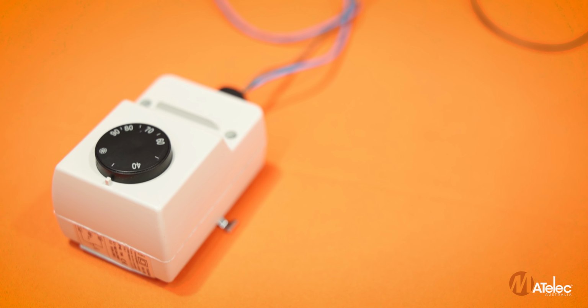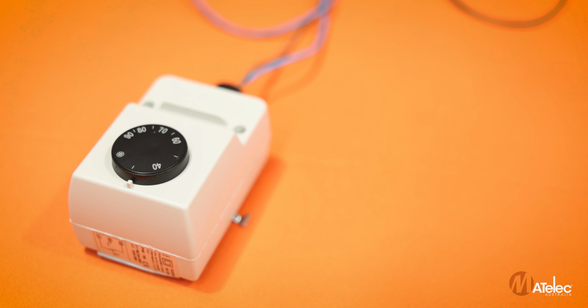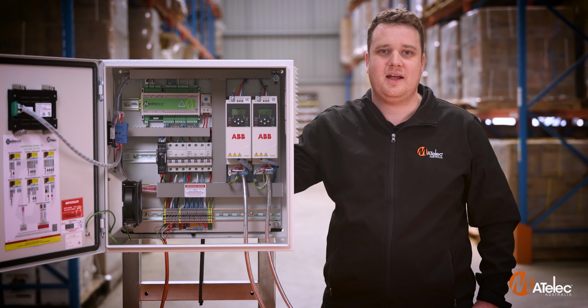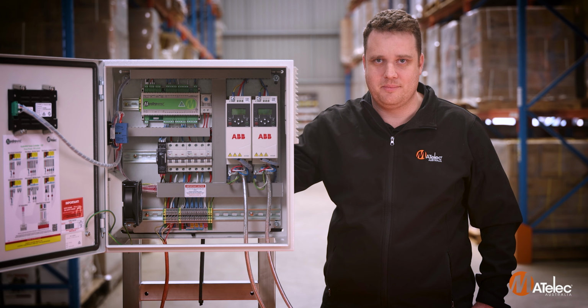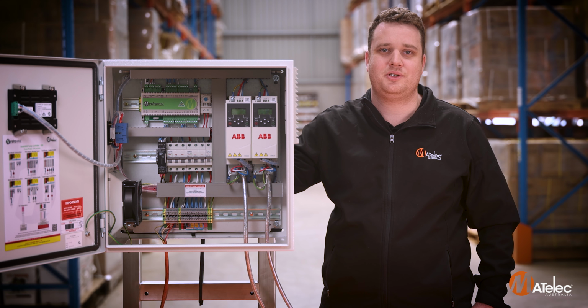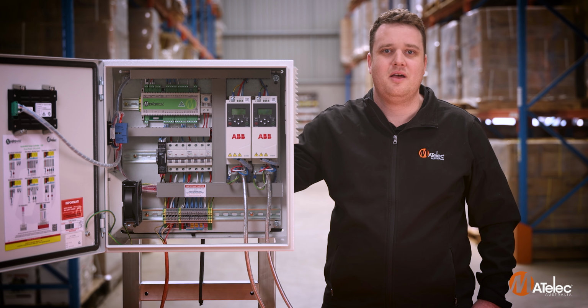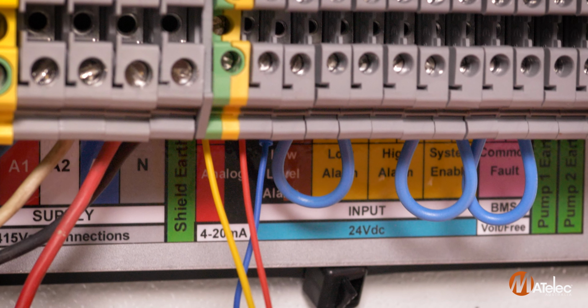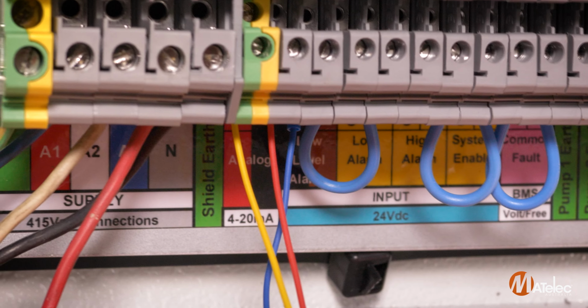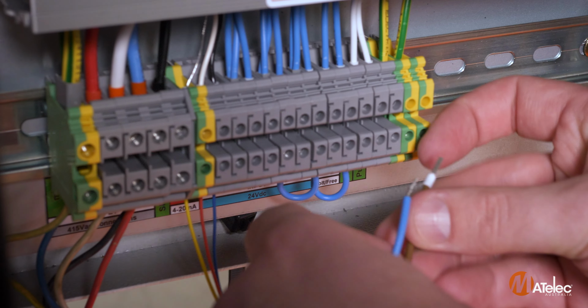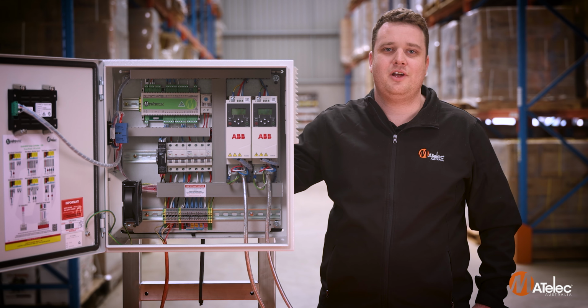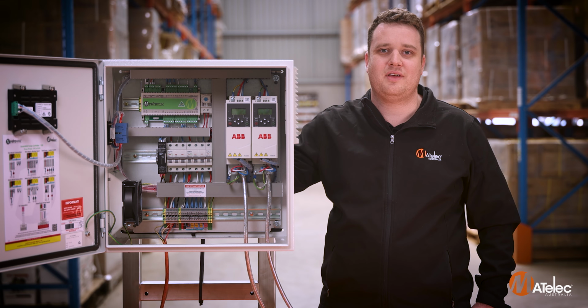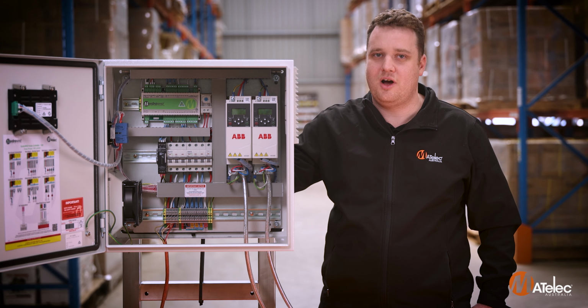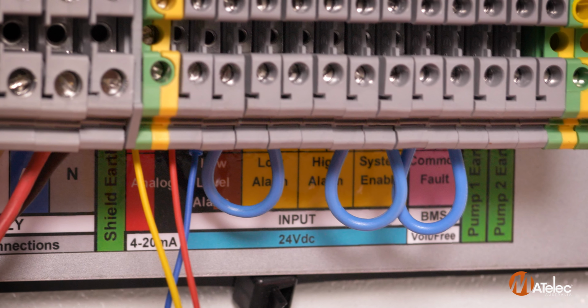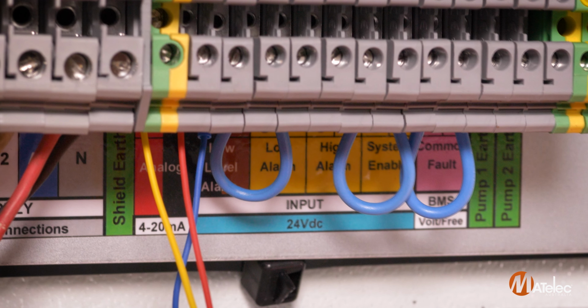2 digital input terminals are provided for high and low temperature thermostats, which act as backup to start and stop the pumps and trigger alarms if the temperature gets too low or too high. Make sure there's a bridge in the terminal marked low level alarm, then connect the high and low temperature thermostats to the high and low alarms respectively. If you don't need a low temperature alarm, leave that terminal open, and if you don't need a high temperature alarm, it should be bridged. We will unassign these in the parameters later.